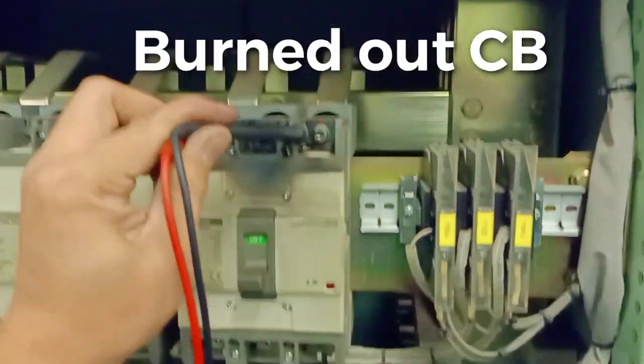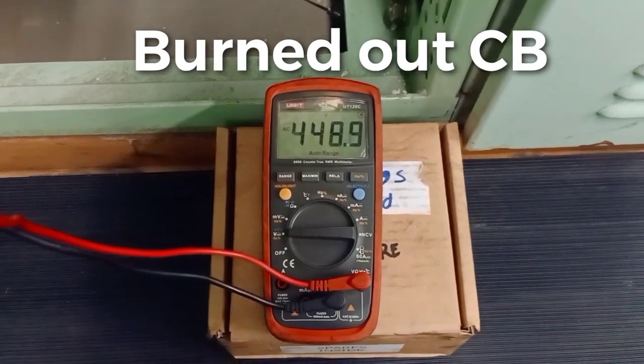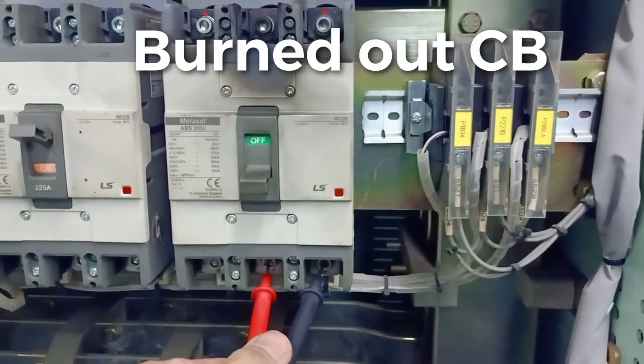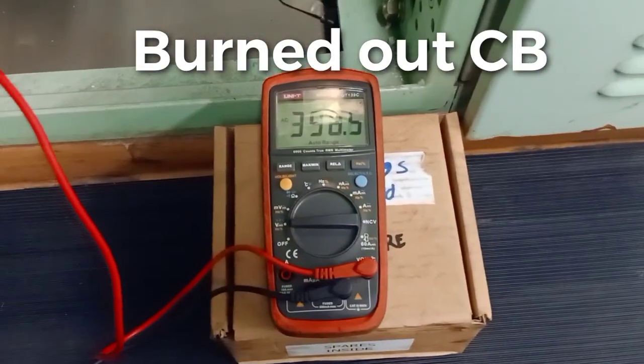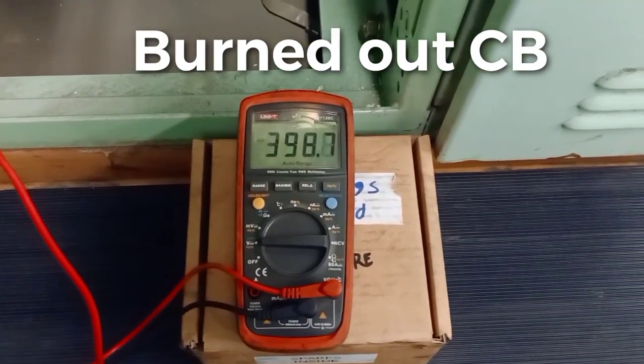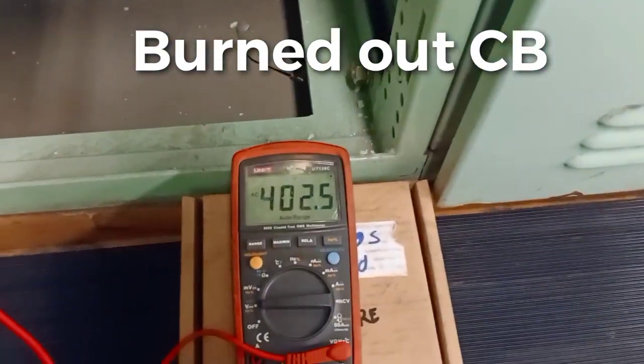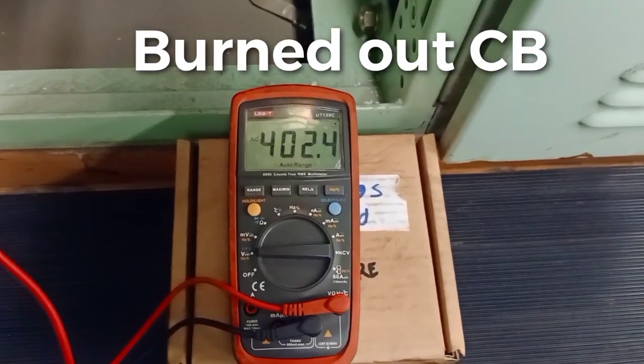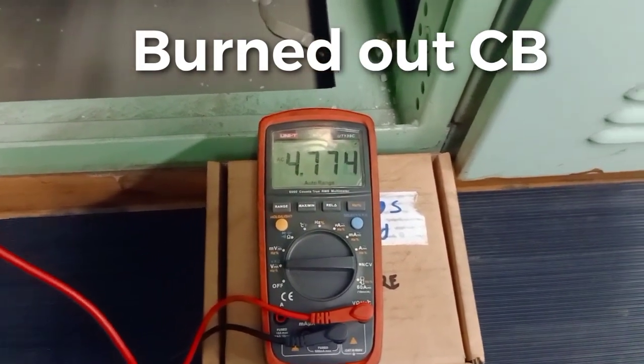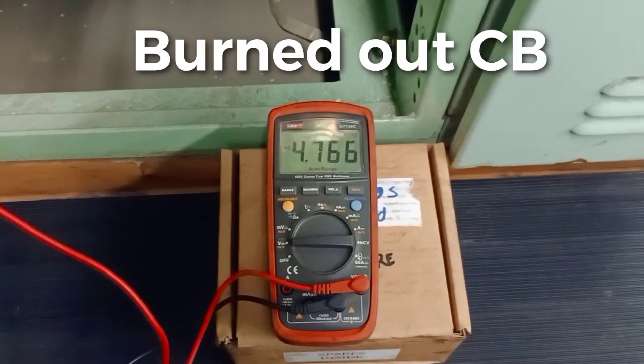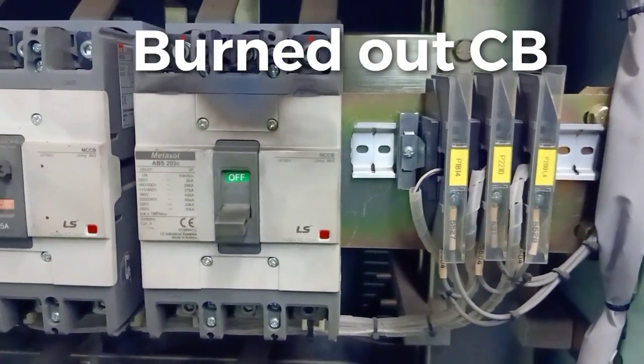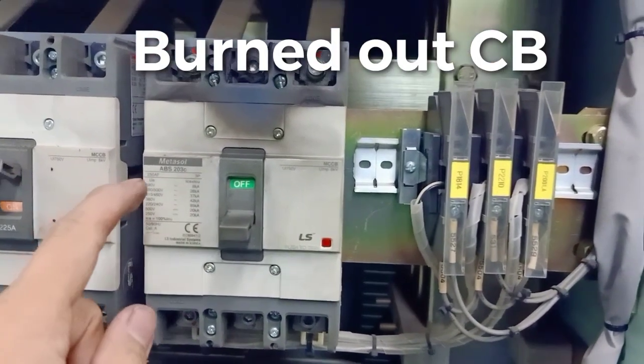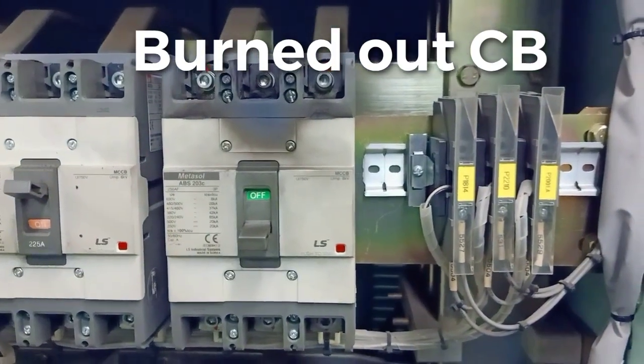Check first from the line side. Working. Next. Working. Next. It's working, 440 volts power supply. Now from the load side, 398 volts. Oh, something wrong. Next. Oh, it's only 402 volts. Something wrong. Next. Oh, 4.7 only. So this circuit breaker is exactly a single phase, working only with a single phase. It is necessary to replace this circuit breaker.